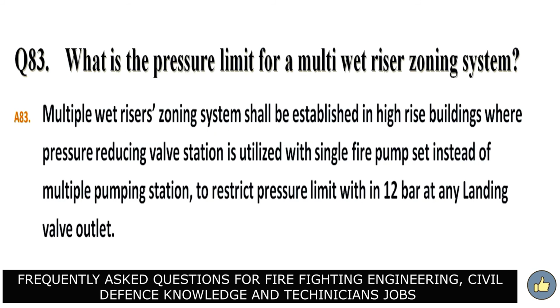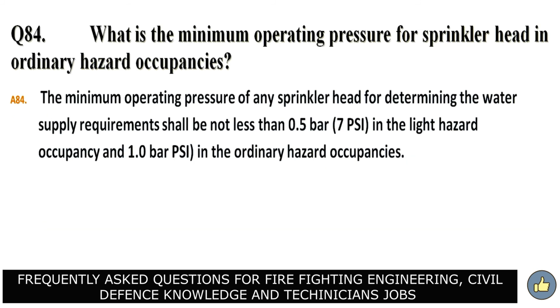What is the pressure limit for a multi-wet riser zoning system? Multi-wet riser zoning system shall be established in high-rise buildings where pressure reducing valve station is utilized with single fire pump set instead of multiple pumping station to restrict pressure limit within 12 bar at a landing valve outlet. What is the minimum operating pressure for sprinkler head in ordinary hazard occupancies? Answer. The minimum operating pressure for any sprinkler head for determining the water supply requirement shall be not less than 0.5 bar (7 psi) in the light hazard occupancy and 1.0 bar in the ordinary hazard occupancies.